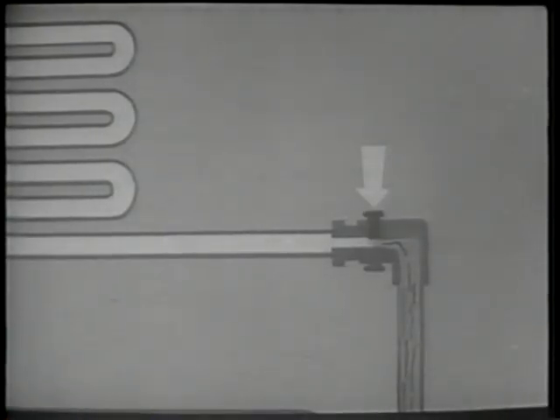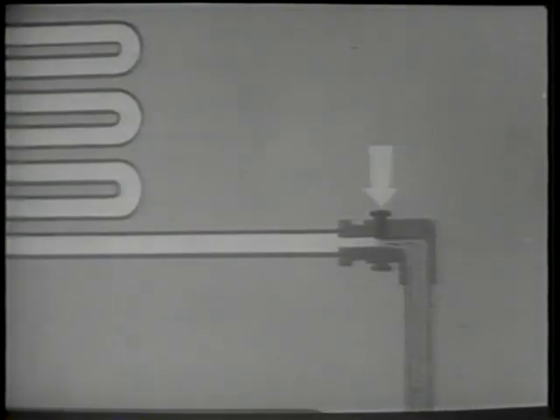The high-pressure refrigerant must now be reduced to a low-pressure liquid so that it can evaporate at a low temperature. The refrigerant passes through an expansion valve, which divides the high and low pressure sides and controls the flow of refrigerant into the cooling unit. The refrigerant enters the cooling unit under a reduced pressure caused by the suction stroke of the compressor.